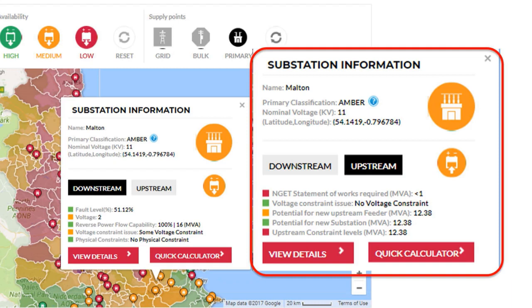So we have to talk to National Grid, who own the national transmission network, and discuss the impact of generation on our network and on theirs. If a site is particularly sensitive to that, the amount of generation that can connect before we need that conversation with National Grid will be very low. In this case, any generation connecting to this substation greater than 1 MVA would need that conversation with National Grid.